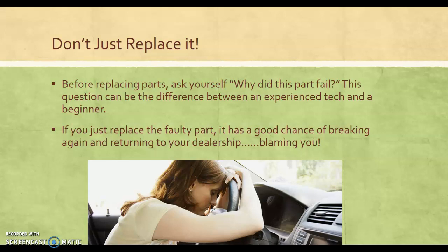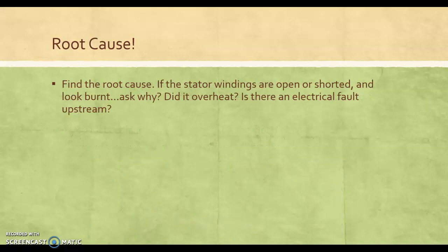Okay, if you're replacing a faulty part, it'll break again, come back, blame you, fix it right the first time scores go down, and the customer satisfaction surveys go down, the dealership gets dinged. No, nobody wins. So make sure you find out why it failed. So find the root cause. If the stator windings are open or shorted and look burnt, ask why again. Back to why did it fail?